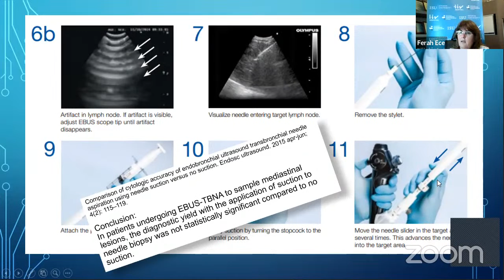Then move the needle slider into the target several times, at least 5 to 15 times. Then the procedure is completed. Turn the stopcock to release the suction. Remove the syringe. Pull the needle slider upwards until it clicks.